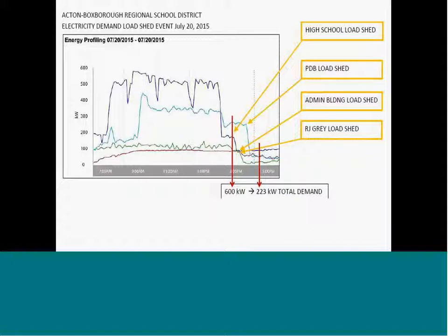If you move to the right, the boxes with yellow arrows point at shifts that happened as a result of the load shed. I've drawn a red line to show we were at 600 kilowatts of demand when the load shed event began. The first building that drops is the big blue one, our high school. Then the much smaller green and red buildings drop, and then the turquoise building drops.